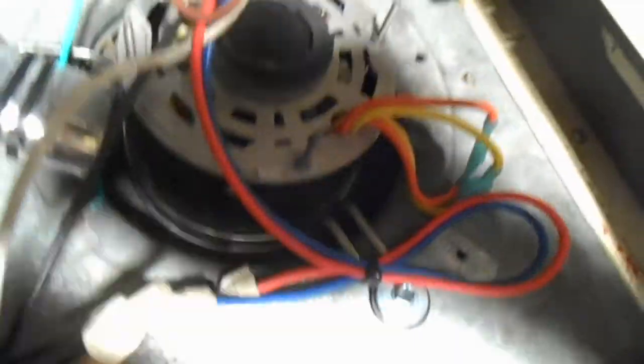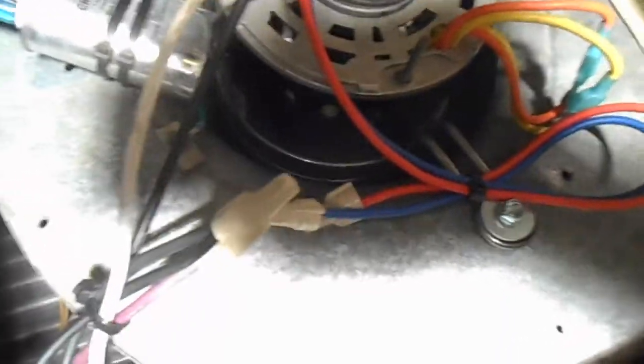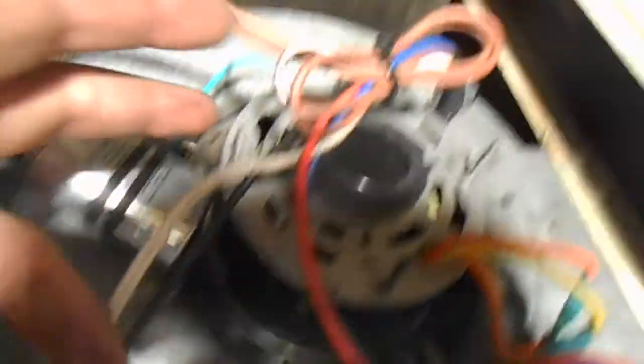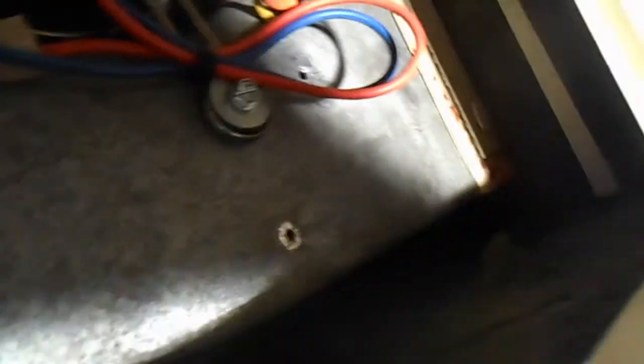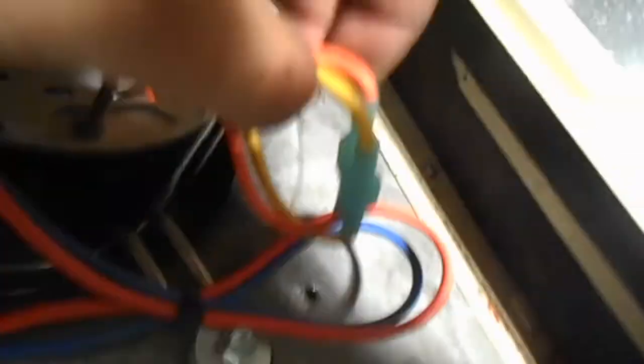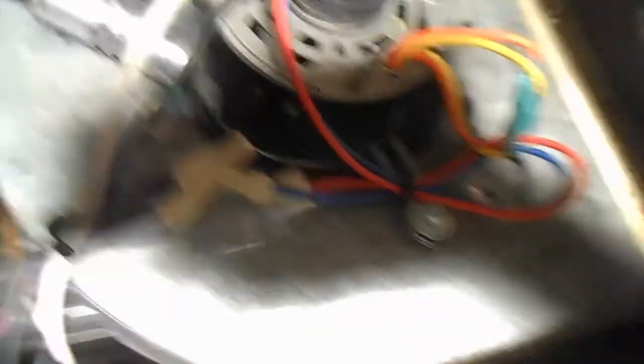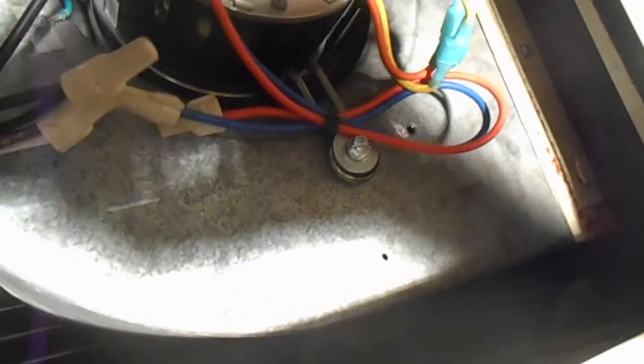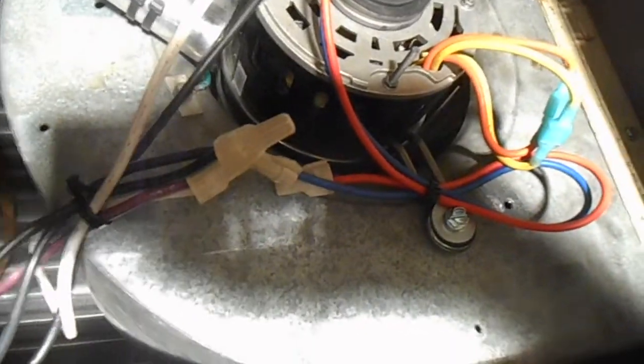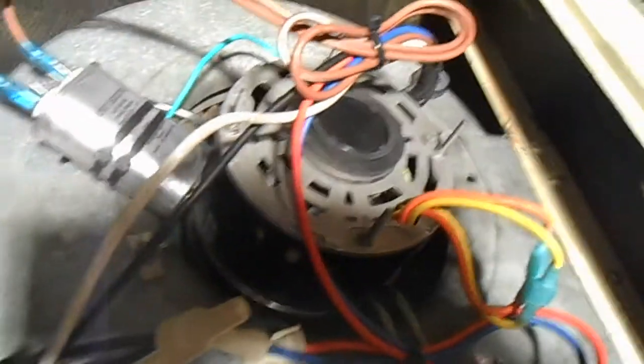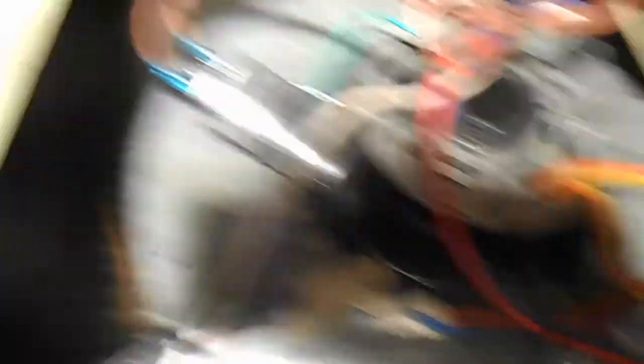Just got this capacitor secured over here. We ended up having to put a new belly band on here because the old motor was shorter and it was at the end of its adjustment already. So we bought a new band, relocated it, new capacitor. Pretty sure it's blowing the right way, but if not it's reversible. So I'll put the panel back on and check the return grill to make sure it's sucking. If not we just swap those two bad boys and we're in business. So that's how you change a fan motor on a packaged water source heat pump.